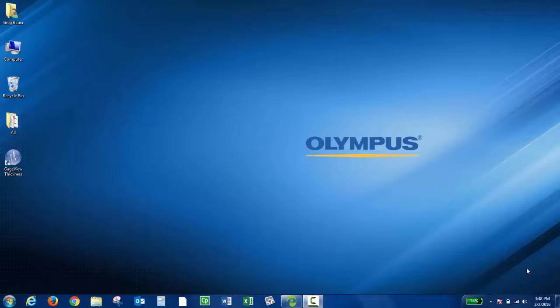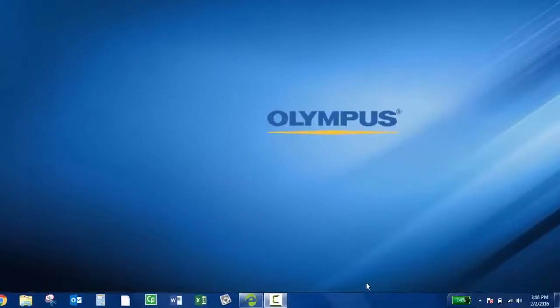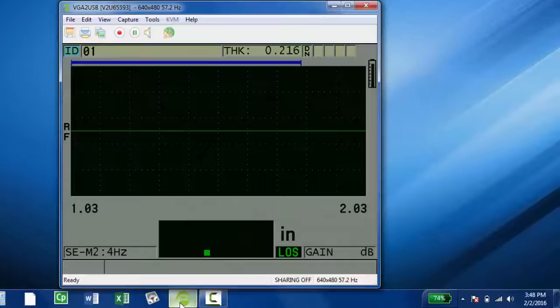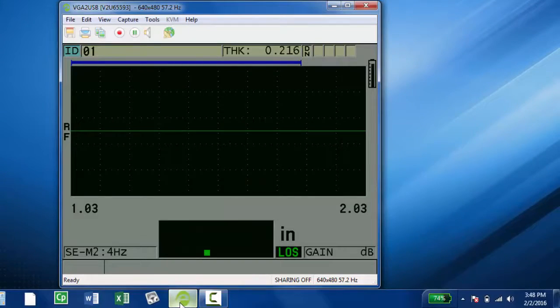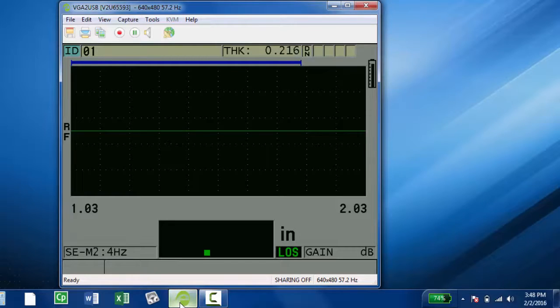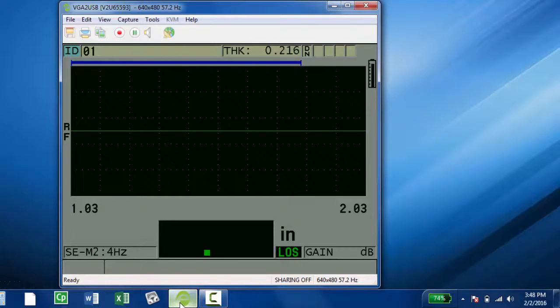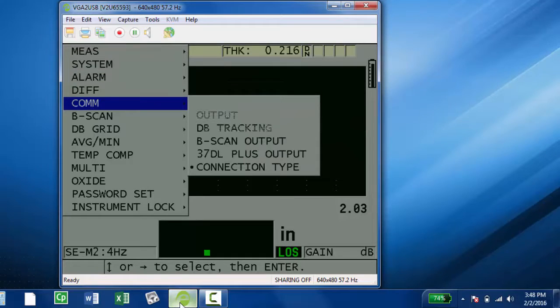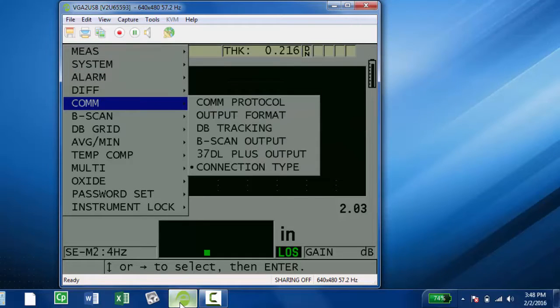The first thing you'll want to do is verify the communication settings on the instrument. I'm using a VGA to USB adapter so you can see the screen of my instrument. Press the Setup menu key, then press the down arrow to COMM, and press Enter.